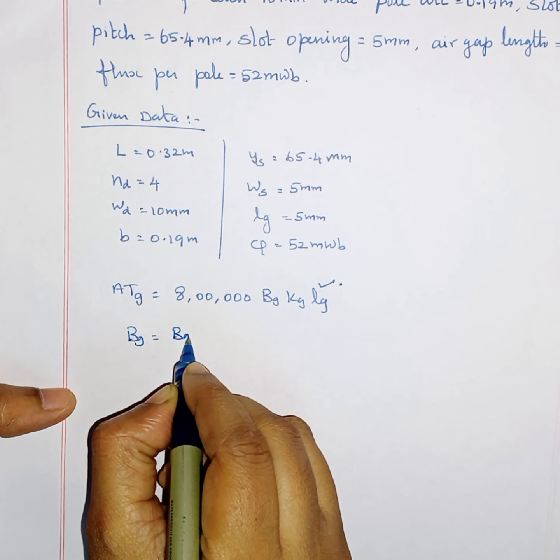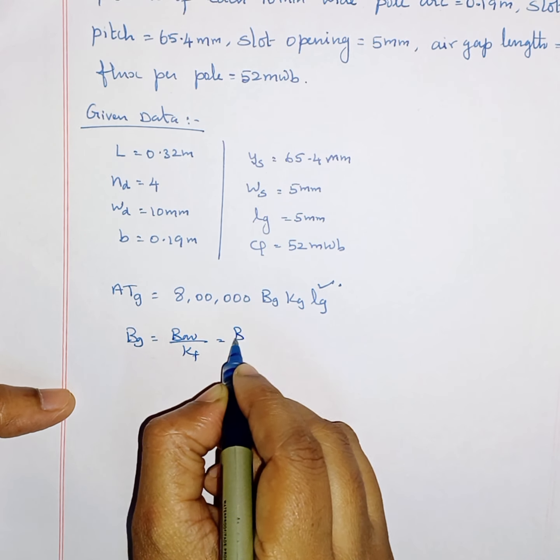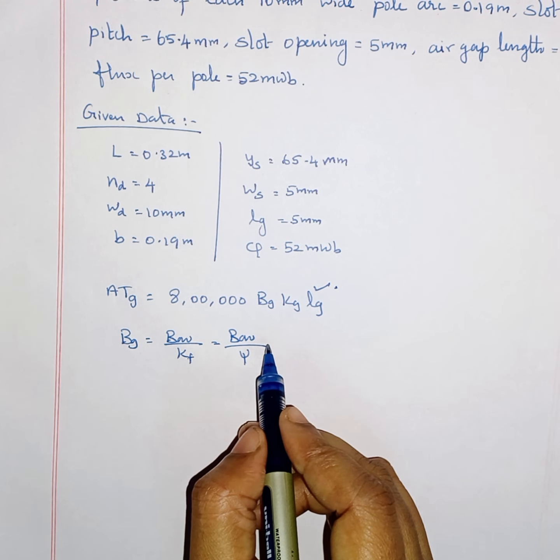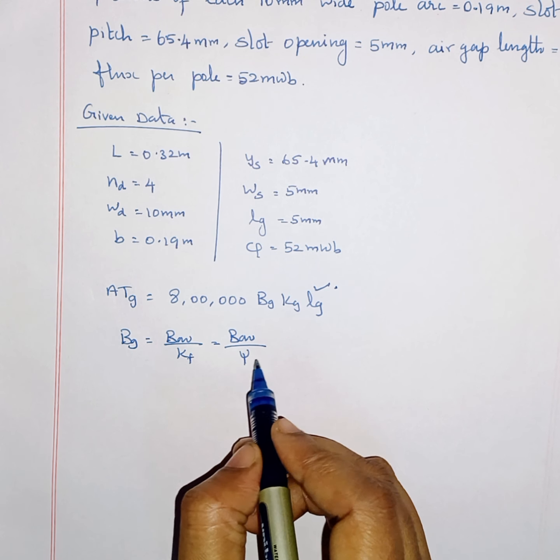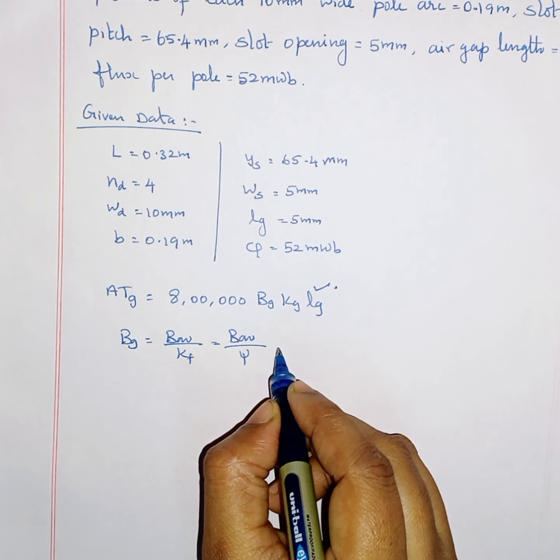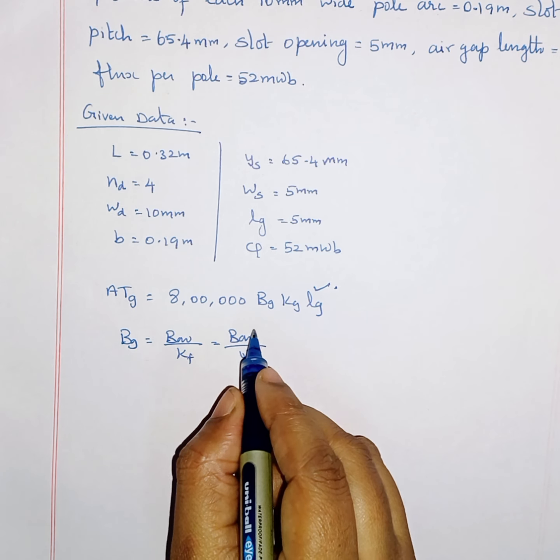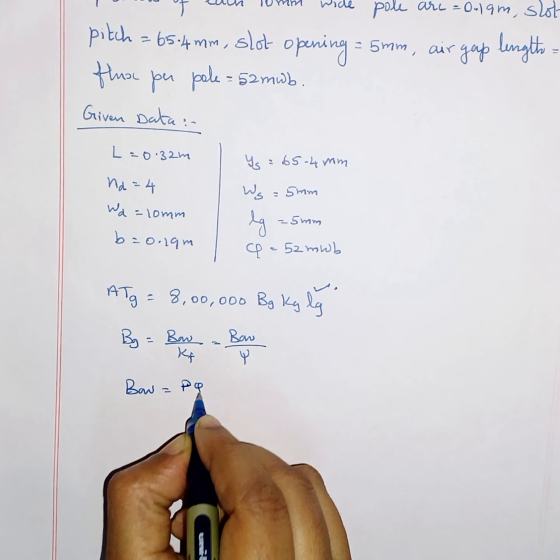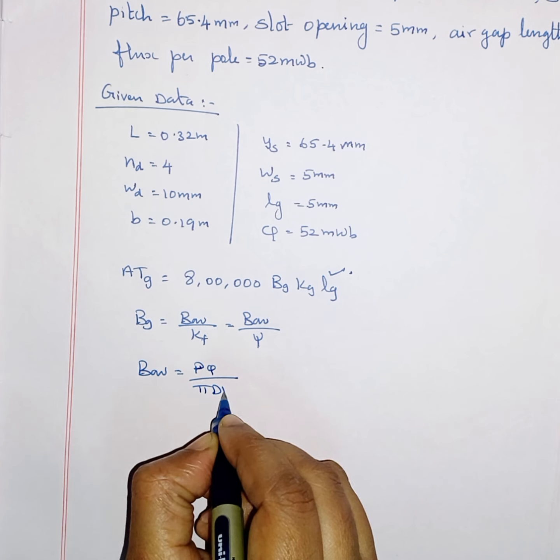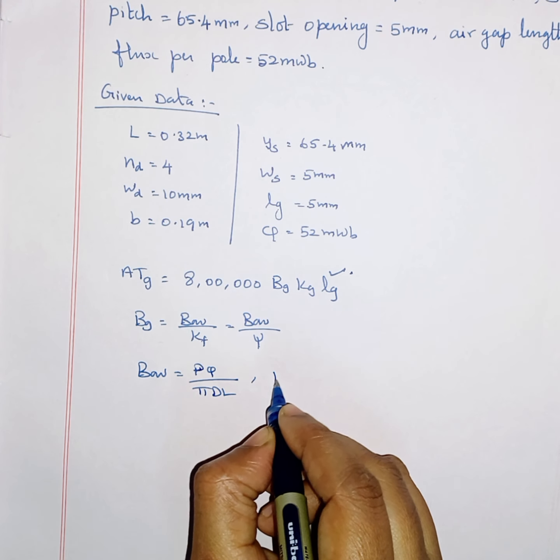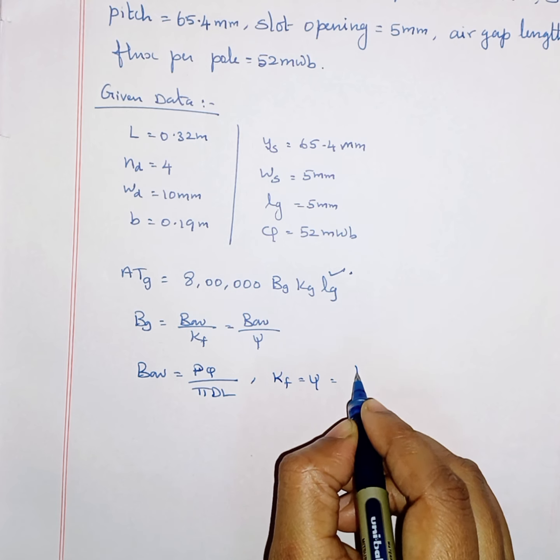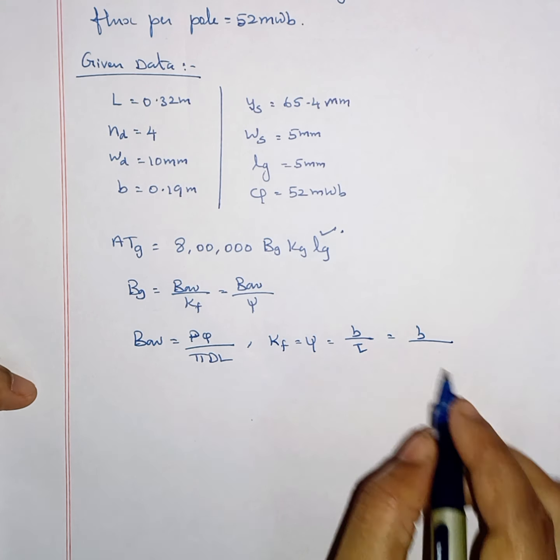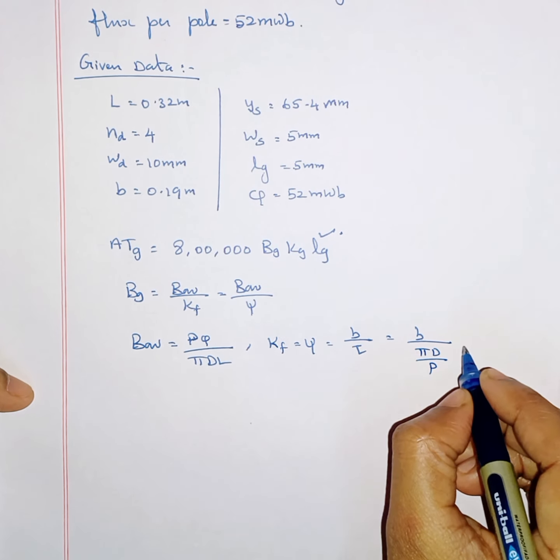First we will find out BG. We know BG equals BAV divided by KF, or BAV divided by psi. Average flux density is not given here and the form factor is also not given, so we will substitute the formula for BAV. BAV is equal to P·φ divided by π·D·L, and form factor KF, which is psi, is B divided by tau — pole pitch is π·D divided by P.